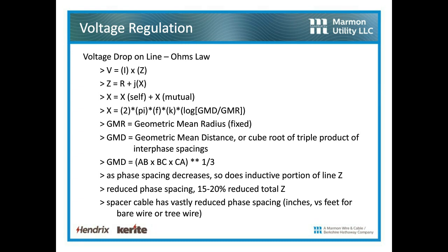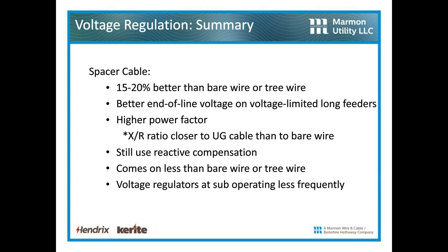So if we look at that summary, the spacer cable is going to give you 15 to 20% better voltage drop than bare wire or tree wire.